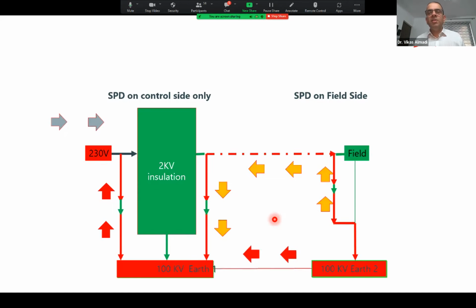Now when we talk about SPDs, there must also be a question. One of the reasons why we should not have two earths is this too, apart from human safety, because that is the prime reason for having one earth. But if you connect the earth together, that is the best situation, because then you reduce the level of current flowing through the SPD or through the equipment. It then depends upon the resistance and the length of the cables, because as I mentioned, length of the cable plays a role. So there will still be some current going, which may still lower down, and it can even help us reduce the capacity of the SPDs also.